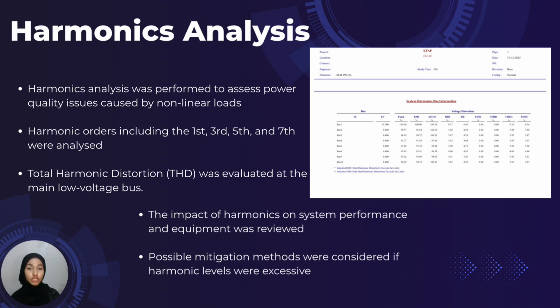The total harmonic distortion, or THD, was evaluated at the main low voltage bus as shown in the system harmonic bus information. The results indicate that the THD levels at the low voltage buses are within acceptable limits based on standard power quality guidelines. The potential impact of harmonics on system performance and equipment, such as additional losses, overheating, and overvoltage distortion, was also reviewed. Although the harmonic levels were acceptable in this case, possible mitigation methods such as passive or active harmonic filters were considered to ensure long-term system reliability, especially under future load expansion.